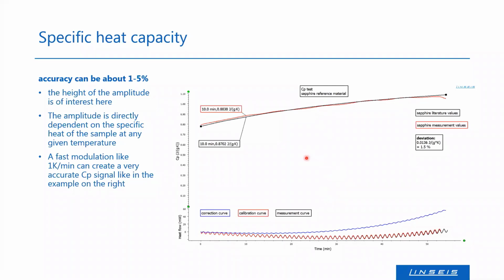So this is also an advantage of this device. The lowest temperature, it's plotted against time now, but we can see it later in our hands-on, is pretty low for a good CP signal. You can measure the CP almost from room temperature, unless of course you have a cooling option. And so you will receive good results really near to room temperature or your starting temperature.